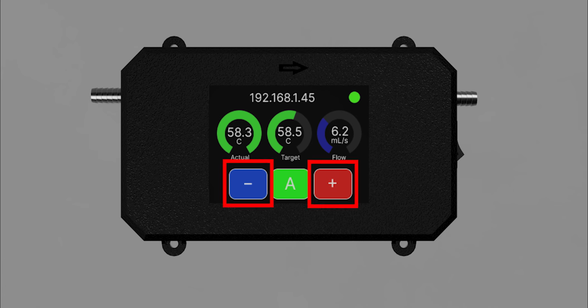The plus and minus buttons, when clicked, will raise or lower the target temp in increments of 0.5. The middle button will have either a green letter A or a red letter M. The green A means the device is in automatic mode. In this mode, ATACC will automatically regulate itself based on the given target temperature. If there is a red M, it means the device is in manual mode.